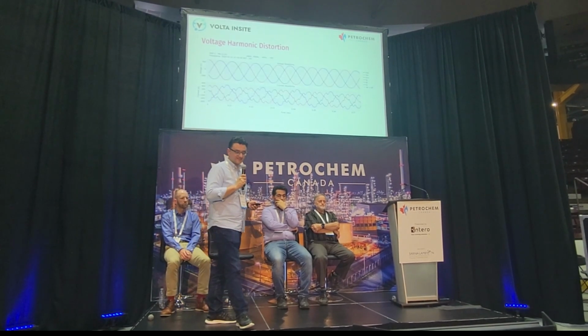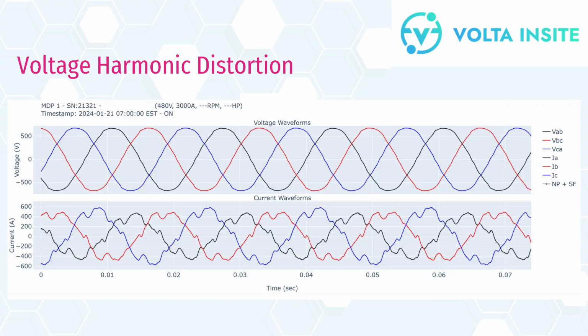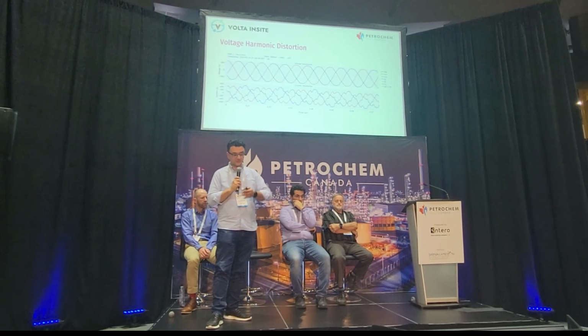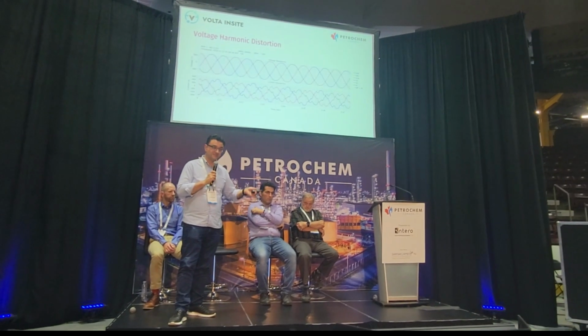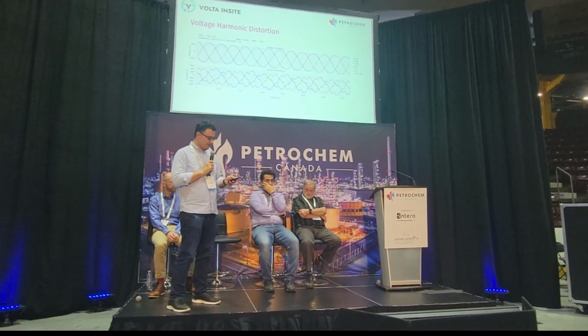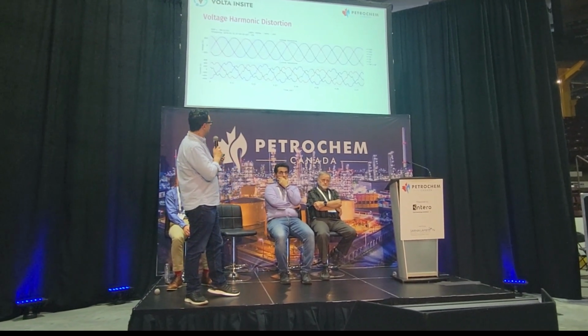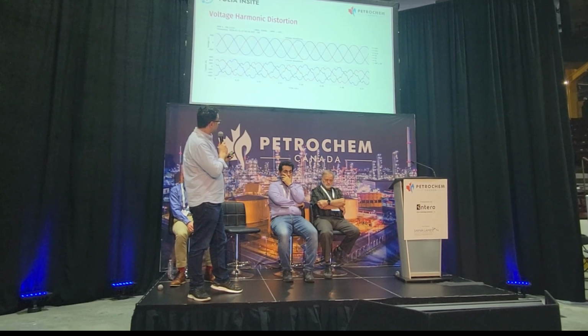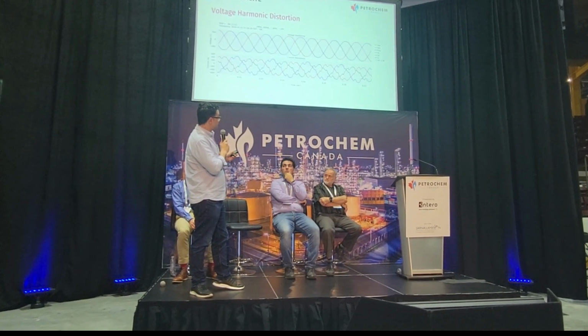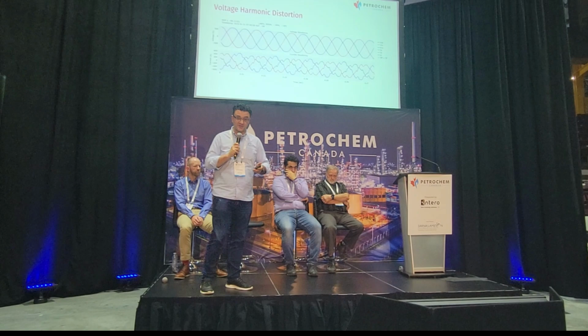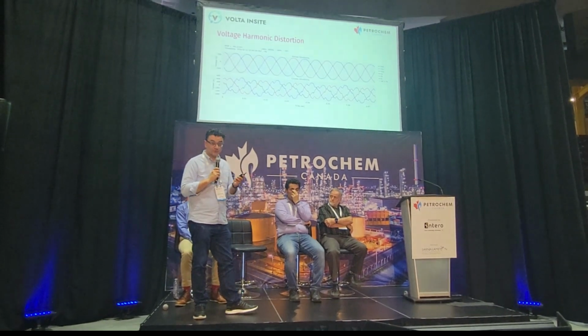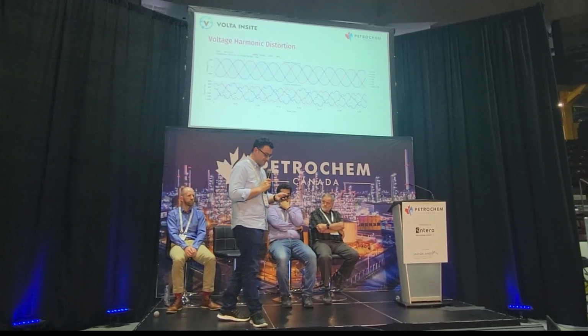This is an example of harmonic distortion within a facility. This is a facility that has a lot of VFDs. The VFDs create a lot of switching noise and effectively put harmonics back in the distribution system. And you'll notice in this case, the voltage is no longer purely sinusoidal, it's slightly off. This may not be a problem for the majority of equipment, but it could have some effects.